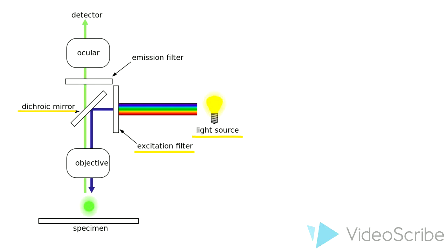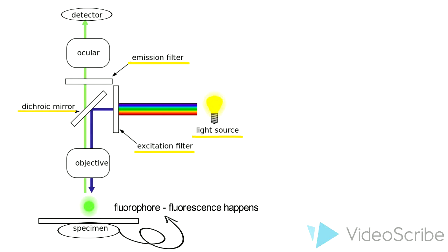After that, the light will reflect on a beam-splitting mirror before reaching the specimen. The fluorescence effect happens here and the specimen emits light with longer wavelengths and lower energy. This emitted light will be filtered again by an emission filter and reach a detector, which can be either human eyes or a digital camera.